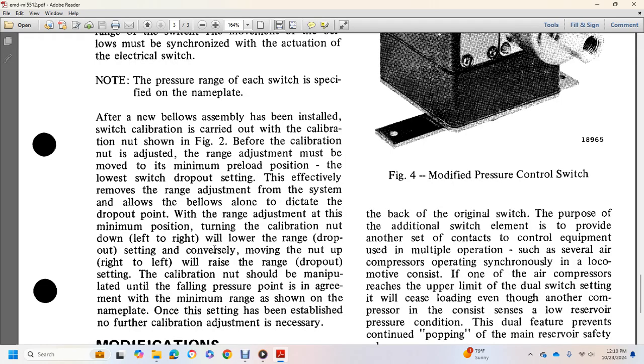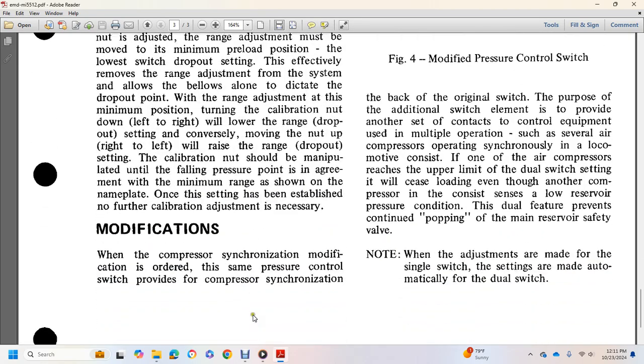The range adjustment must be moved to the minimum preload position when setting the lowest switch dropout, with the effect of removing the range adjustment from the system, allowing the bellows to dictate the dropout point with the range adjustment at minimum position. Turning the calibration nut down, left to right, lowers the range dropout setting. Conversely, moving the nut up, right to left, raises the range dropout setting. The calibration nut should be manipulated to the pressure point in agreement with the minimum range shown on the nameplate. Once the setting has been established, no further calibration adjustment is necessary.